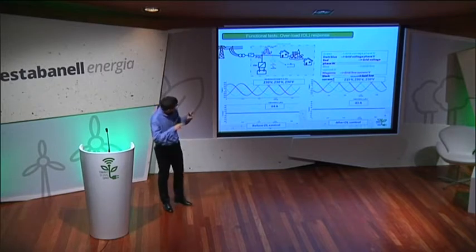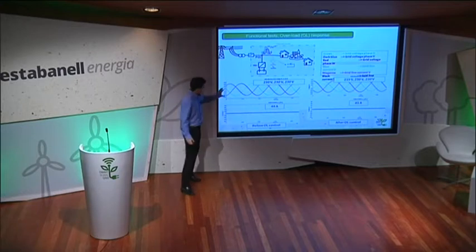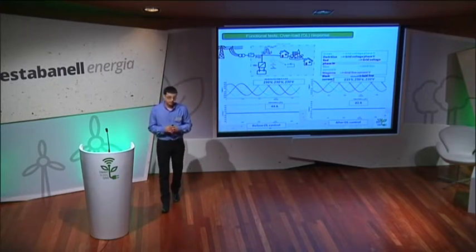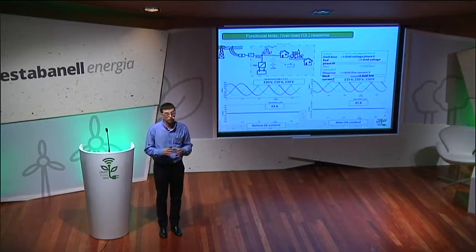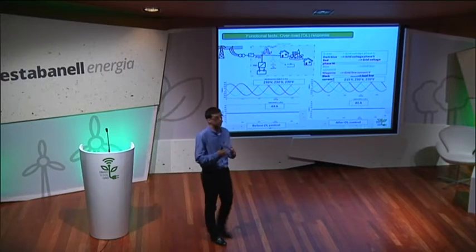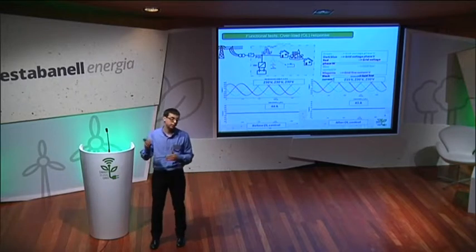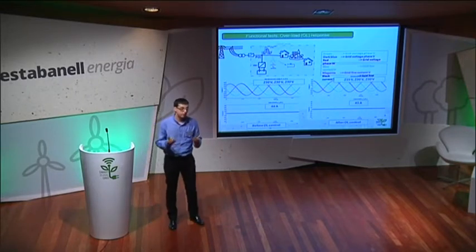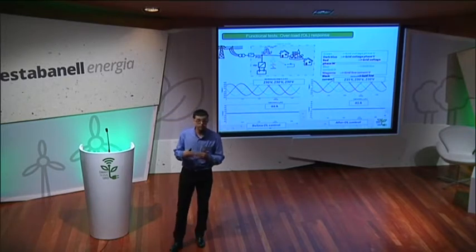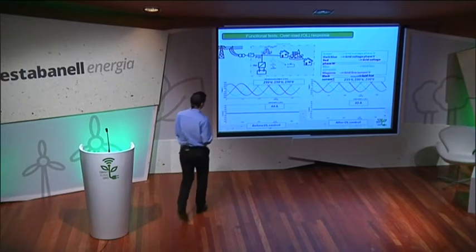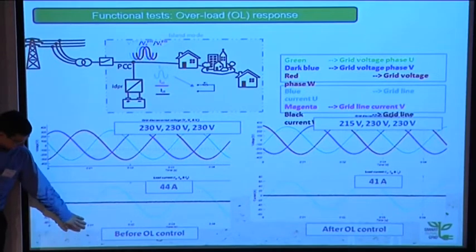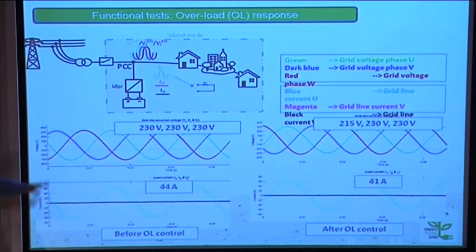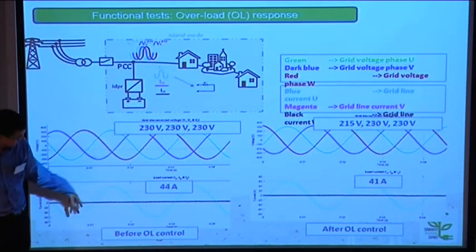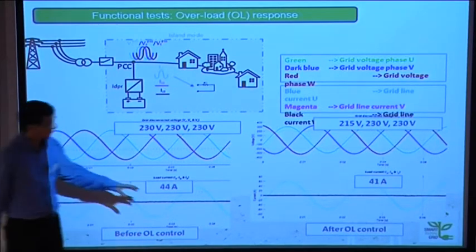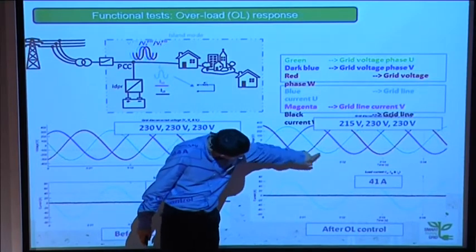One interesting case, it's something moved, but I think that I can explain it. Here we have a similar situation, but if we are operating the system in grid disconnected mode, we also have to ensure that in case of a short circuit or an overload, the system will be able to reduce the voltage according to some preconfigured current, because in that sense, the conventional protective elements will be responsible for disconnecting the fault. For example, before enabling some overload control algorithms that we have implemented, we have 230 volts in each phase. So in case of a fault, we are always supplying the fault, but after activating it, the phase, well, it's the green. I think it's a little bit difficult to see, but there is a reduction in terms of amplitude.